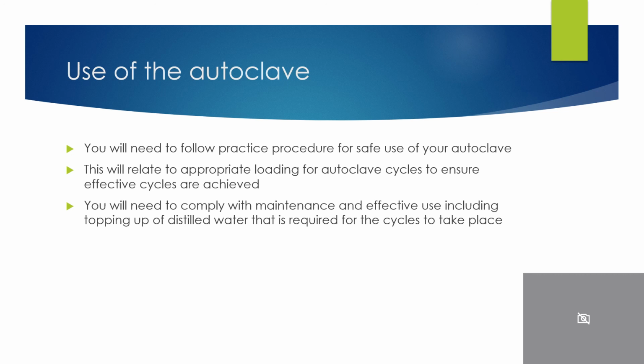Use of the autoclave. You'll need to follow a practice procedure for safe use of your autoclave. There should be a practice SOP relating to it, and this will relate to appropriate loading for the autoclave cycles to ensure that effective cycles are achieved, and also from the point of view of health and safety to help protect yourself from any injuries or harm from occurring. You'll also need to comply with the maintenance and effective use, including topping up of the distilled water, because that is required for the cycles to take place.